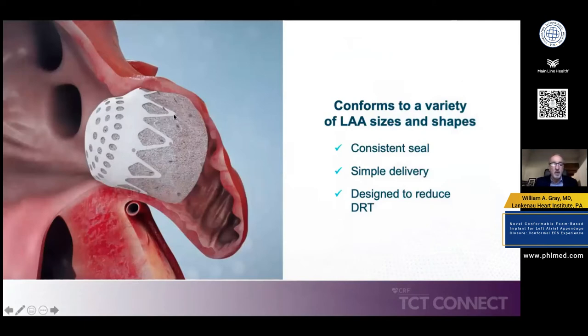The reason this device has such promise is because, as compared to the WATCHMAN, which had all those prongs, this device is covered in a foam shield, which allows it to be very safely exited from the catheter with a bumper, and very difficult to actually injure the myocardial surface. In addition, it has the usual anchor barb system, you can see them here, and it has a Gore-Tex covering which allows for rapid healing. Most people know that EPTFE Gore-Tex has many biological uses, and this is a very consistent material in use. It should also reduce the incidence of thrombosis. And also, in an effort to reduce thrombosis, there's no screw here, which is present in the WATCHMAN device. It actually has a tether, so there's nothing sticking out that's going to allow for thrombus formation.